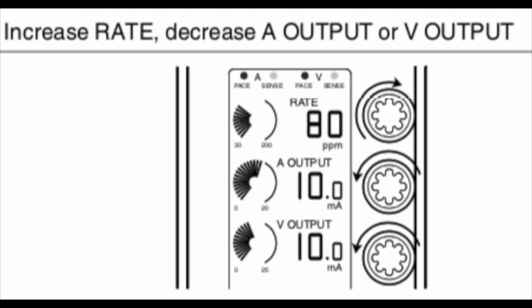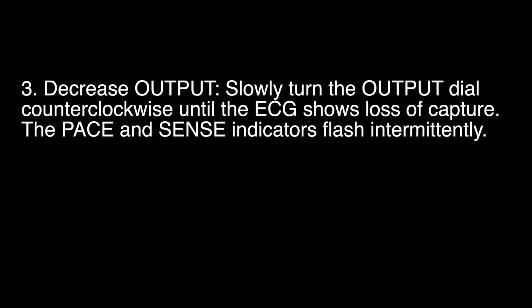Determining atrial or ventricular stimulation thresholds. To determine atrial or ventricular stimulation thresholds, perform these steps. 1. Verify that the patient is connected to the temporary pacemaker and is being monitored on the ECG. 3. Decrease output. Slowly turn the output dial counterclockwise until the ECG shows loss of capture. The pace and sense indicators flash intermittently.